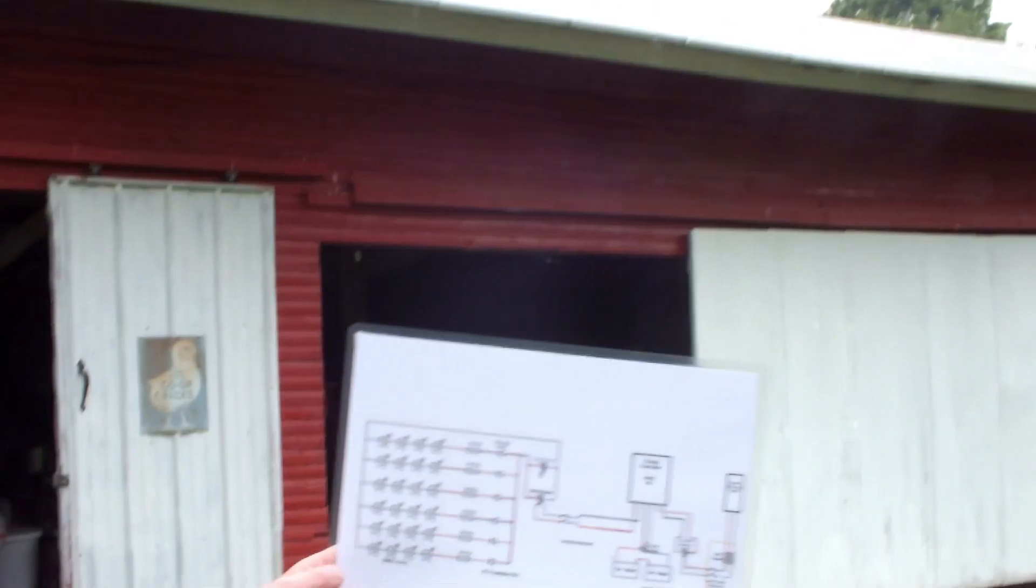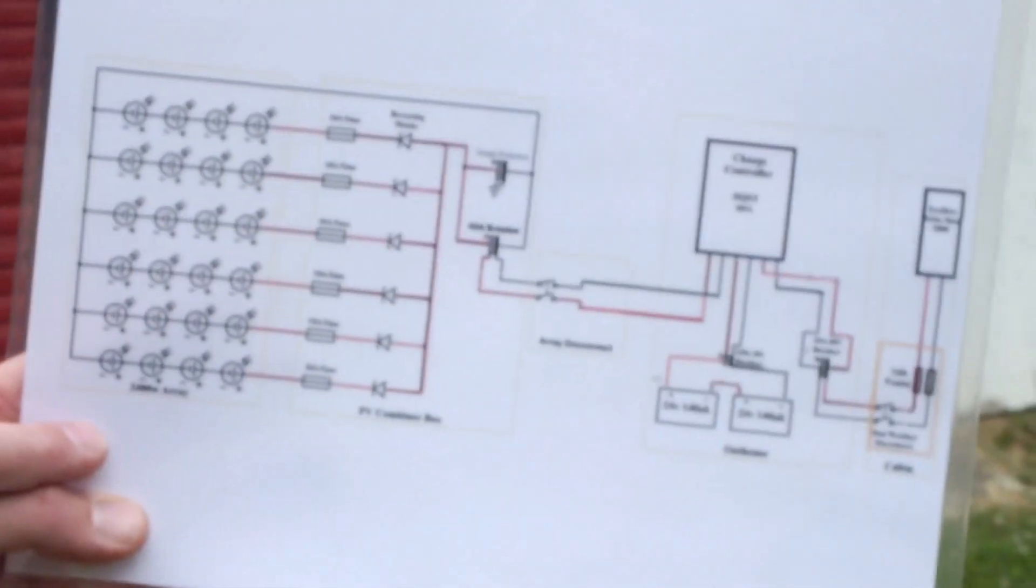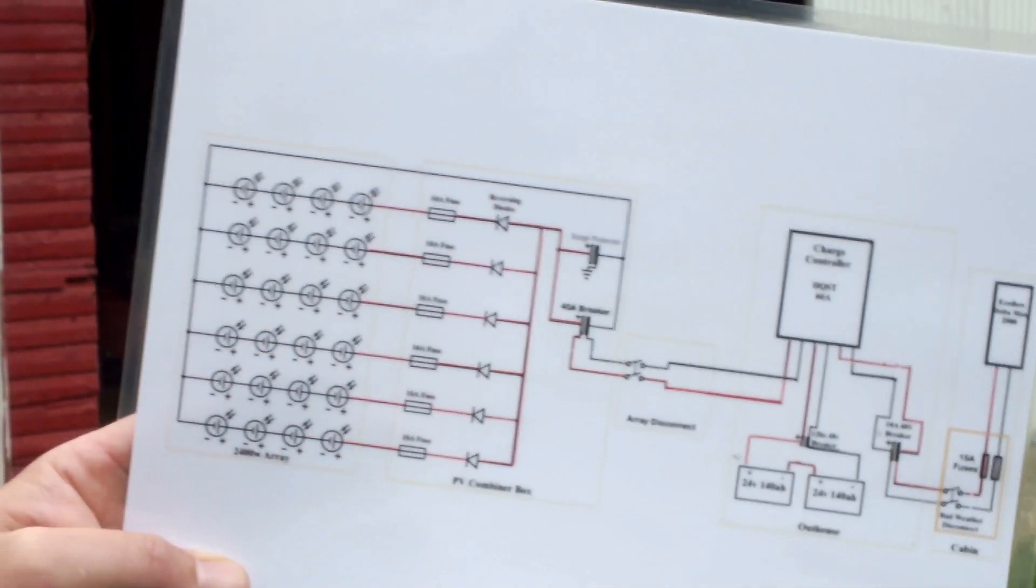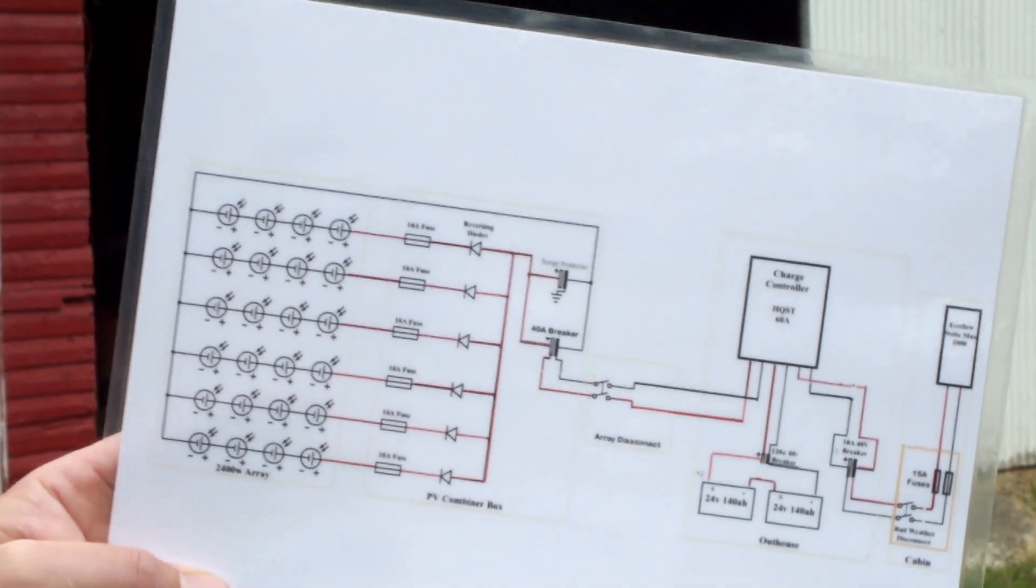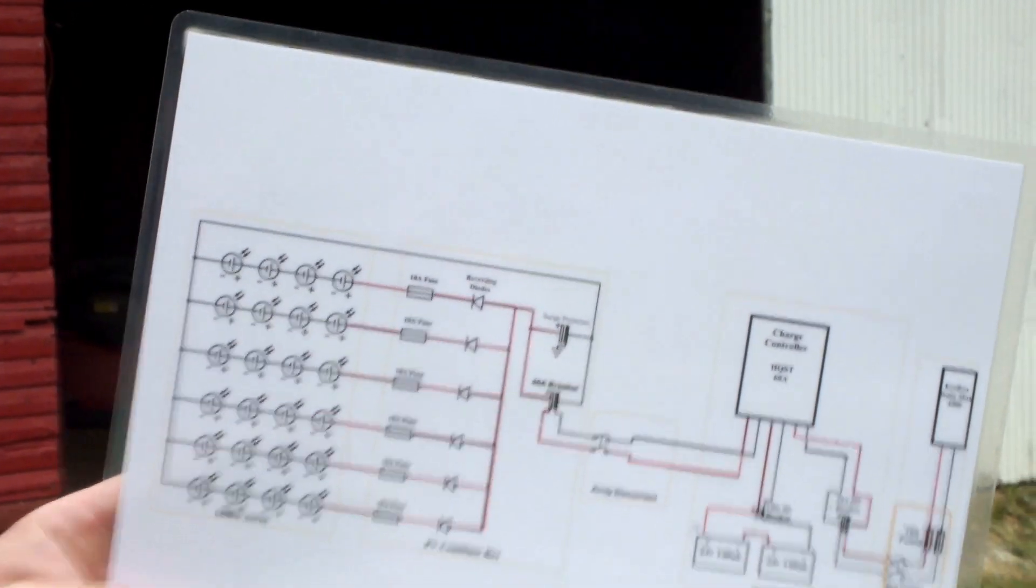If you look here on the array, we have them wired four series, six parallel, giving us an 83 volt 30 amp service. Well, 33 amp. Something to note on the fuses.